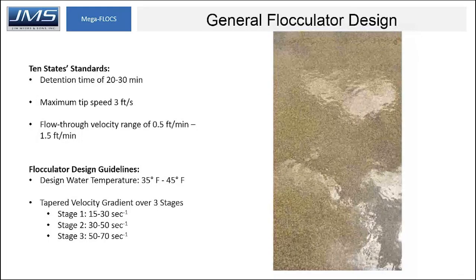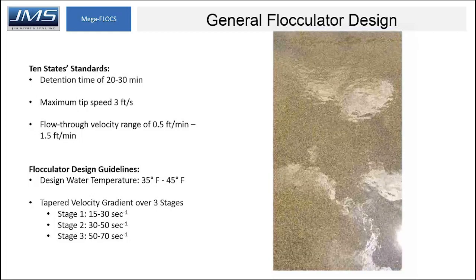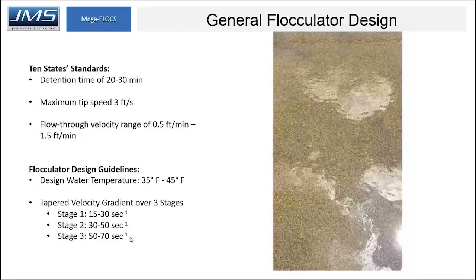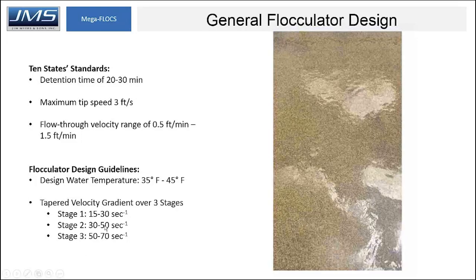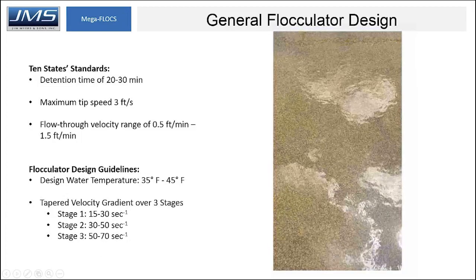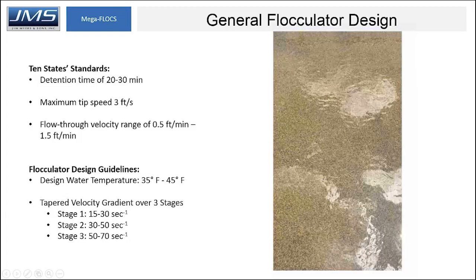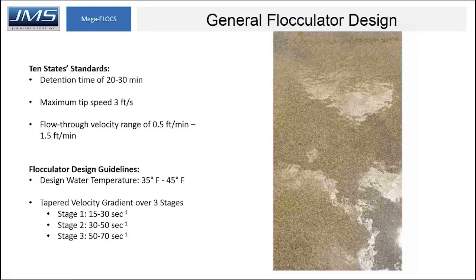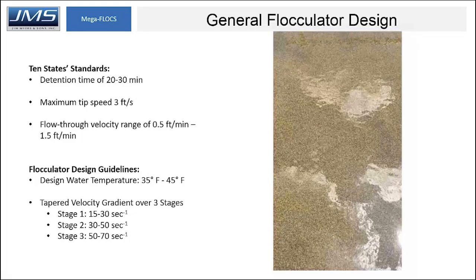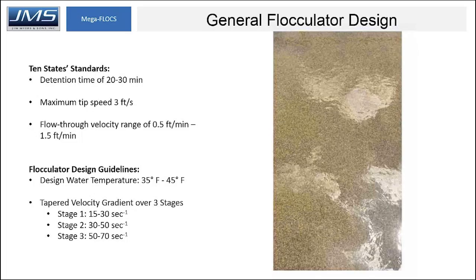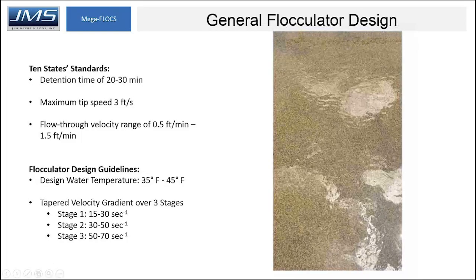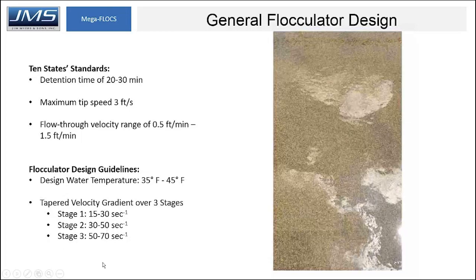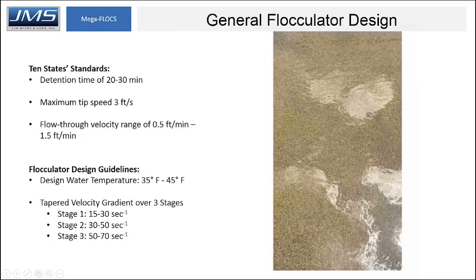No velocity gradient guidelines are given by the Ten State Standards, but for water treatment plants a velocity gradient between 70 to 15 is acceptable and provides the best results. Temperature is also not specified, but typically designed for anywhere between 35 to 45 degrees Fahrenheit. As you can see in this picture, a large, fluffy, easily settable floc particle is the goal of any flocculator.